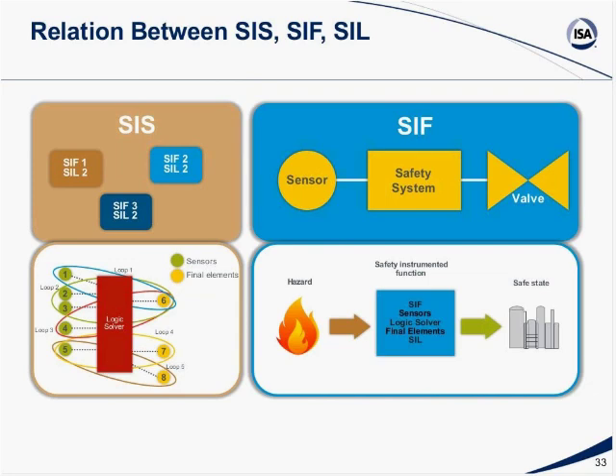So let's look at the relation between SIS, SIF, which is a safety instrumented function, and SIL, which is a safety integrity level. So in this particular diagram, on the right side, you see something which is called an SIF, the safety instrumented function. The SIF basically consists of a sensor, a logic solver, and a valve. So a SIF, sensor, logic solver, and final elements act in concert to detect a hazard and bring the process to a safe state. Like the safety features on an automobile, a SIF may operate continuously like a car's steering or intermittently like a car's airbag. And the safety function operating in the demand mode is only performed when required.